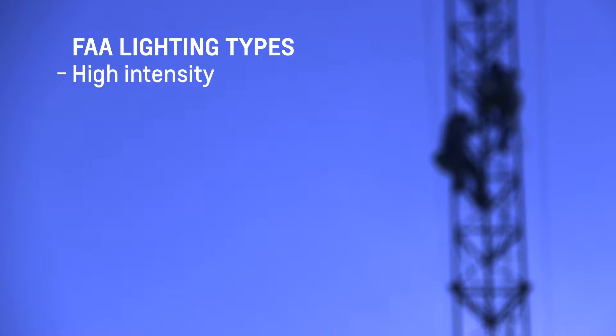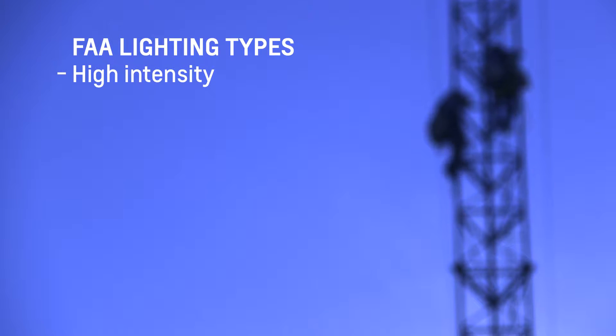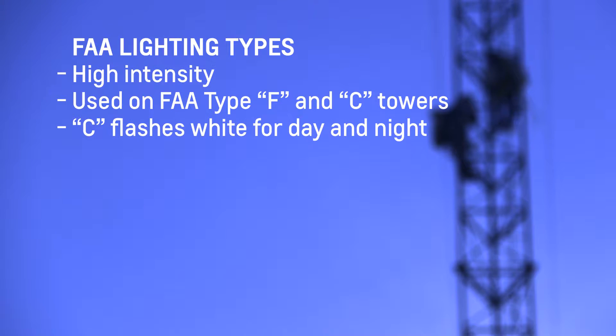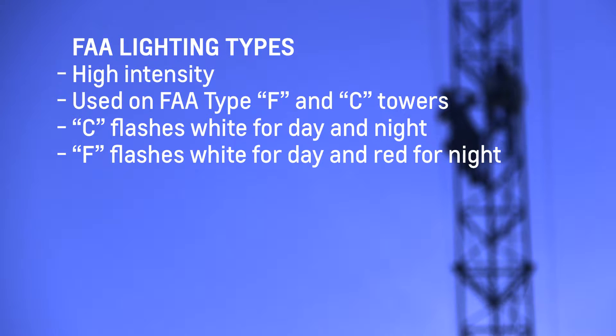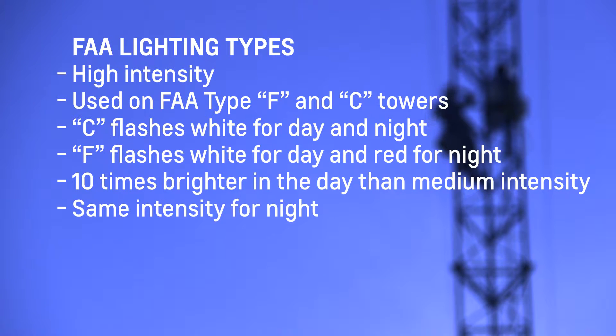High intensity. These are the brightest of the lighting systems and are used on FAA type F and C towers. These towers exceed 700 feet. FAA type F tower lighting flashes white for day and red for night. These systems are ten times brighter in the day than medium intensity systems; however, they utilize the same intensity for night.